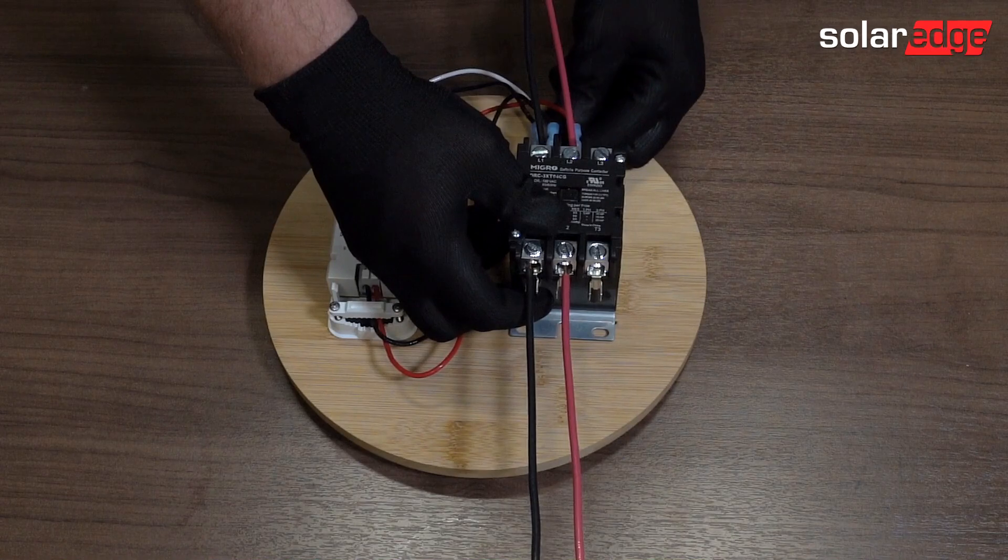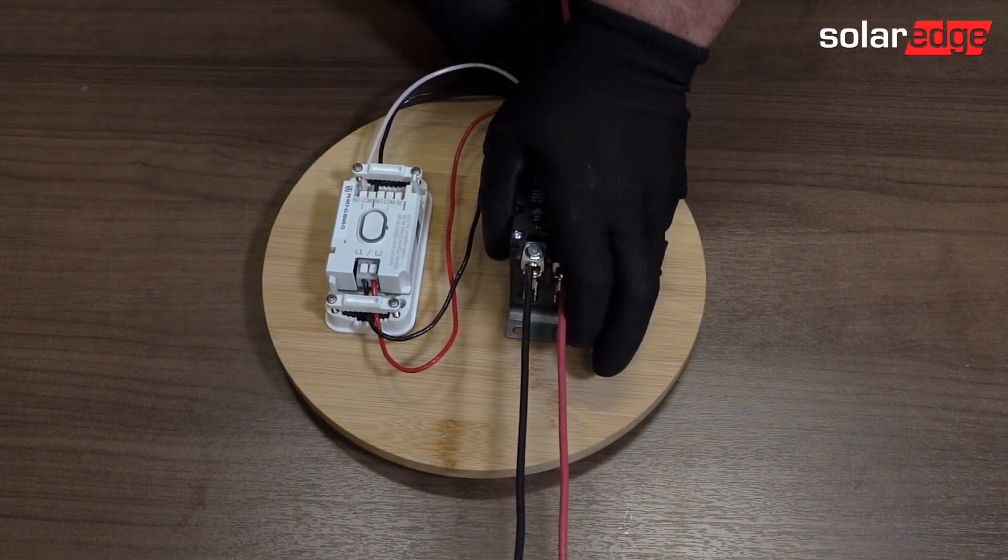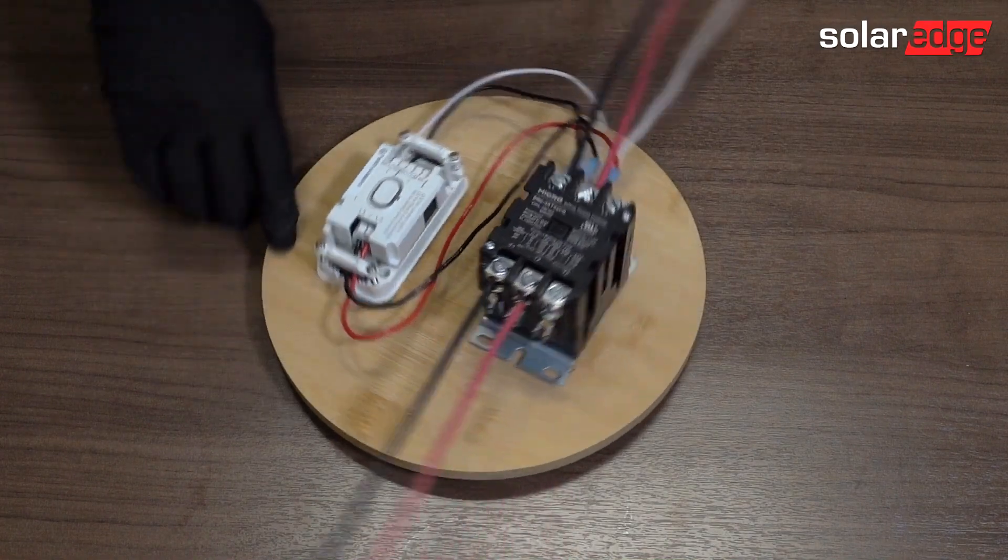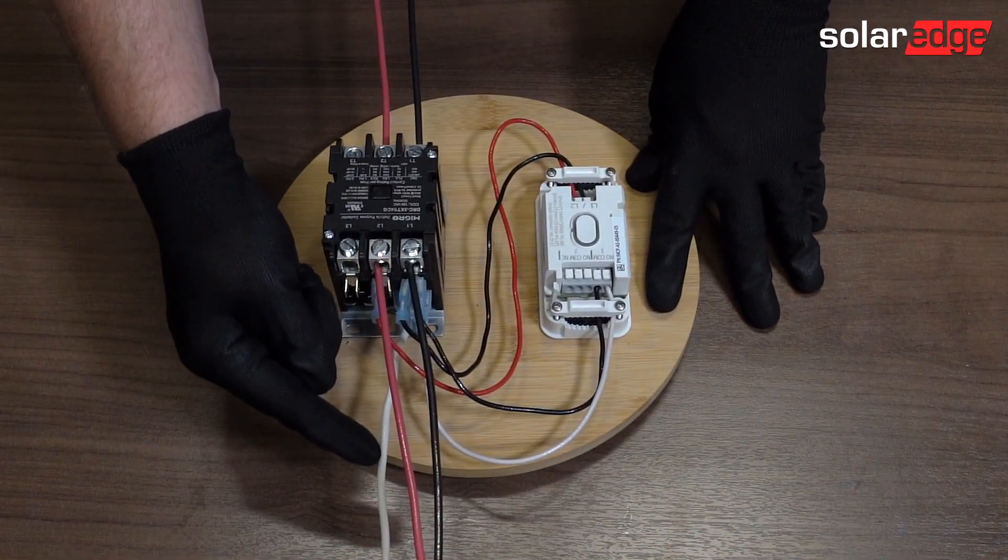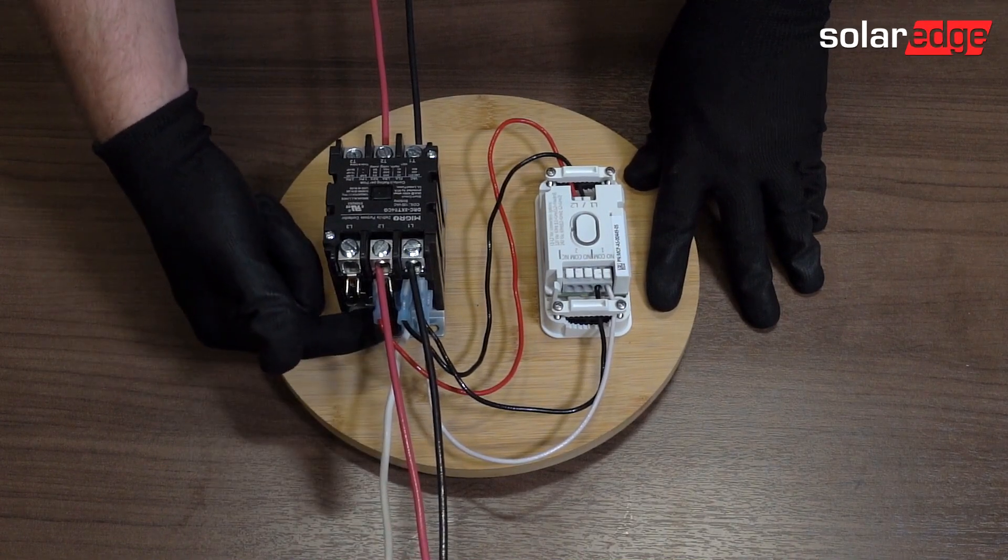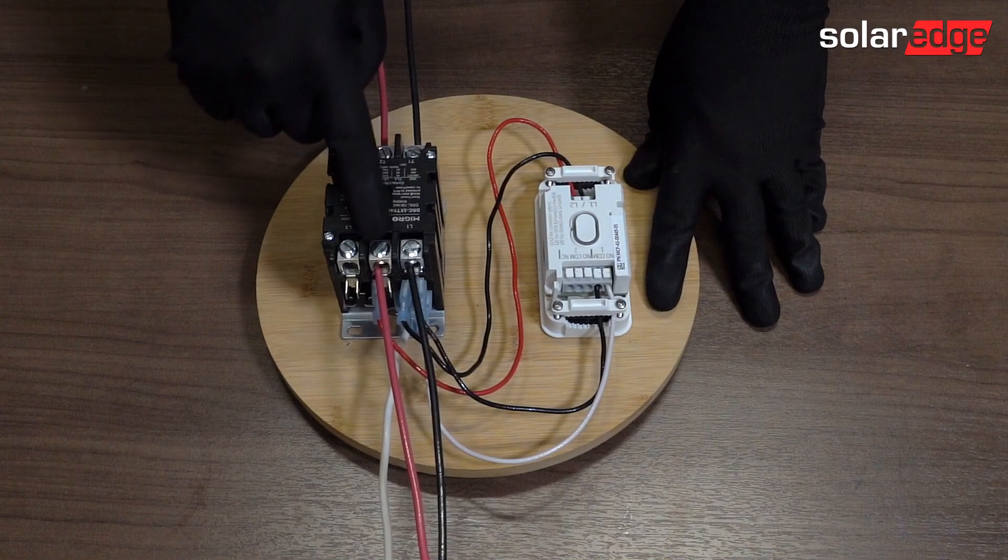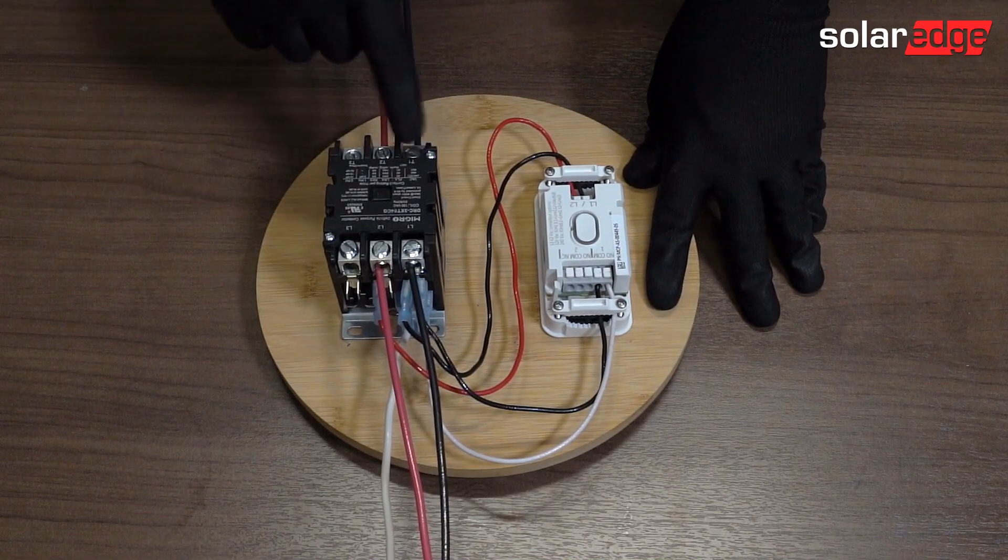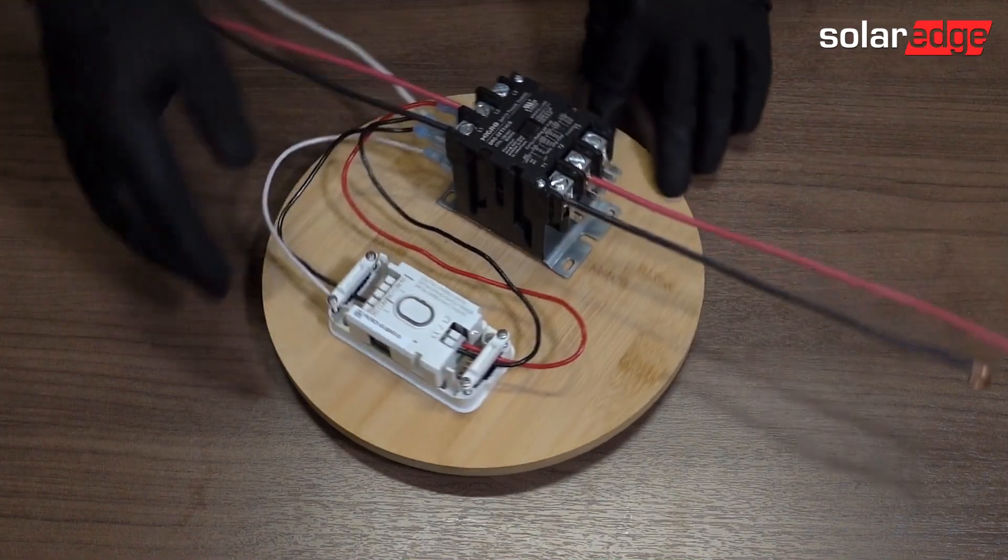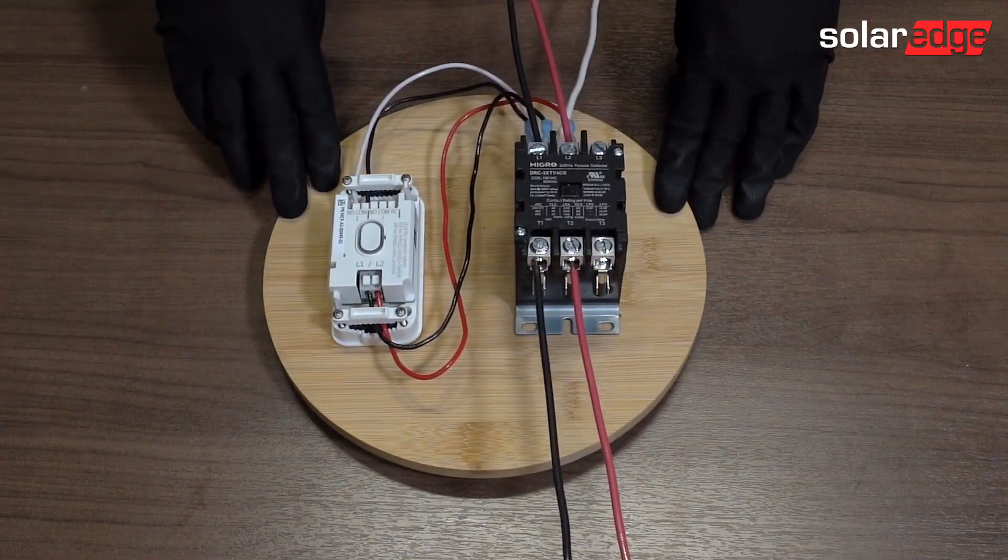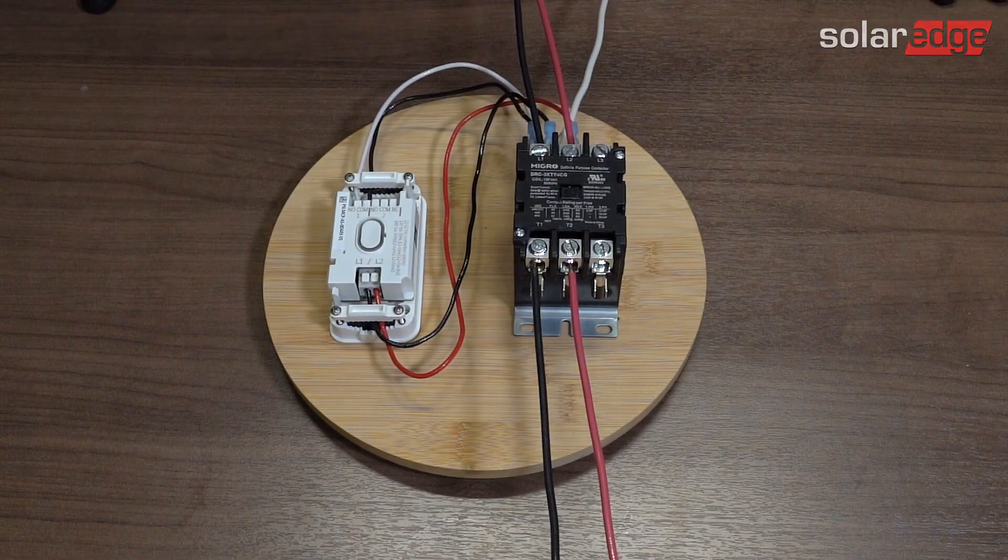And then the last thing, because this is a 120 volt coil, we're going to go from the neutral to the coil on the bottom here. We have our power supply done on line one and line two. And then this goes to our load on line one and line two. And that is how you wire a three-pole contactor to a SolarEdge load controller.